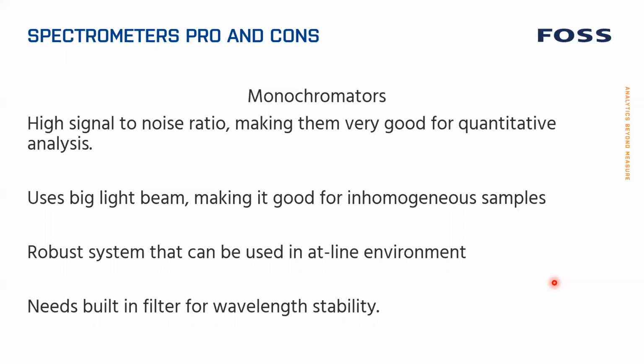And it's even a little bigger when it hits the sample in the DS2500. It's about that size on an Infratech or a FoodScan. So that's really good for inhomogeneous samples. It's also a robust system, so it can be used in a harsh environment. And it uses this built-in filter for wavelength stability, so the instrument will not change over its lifetime.